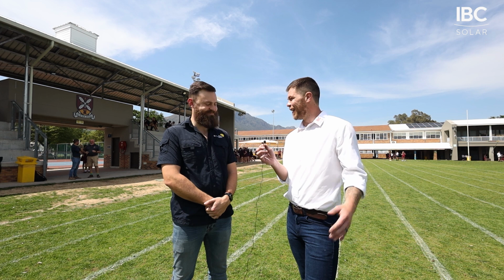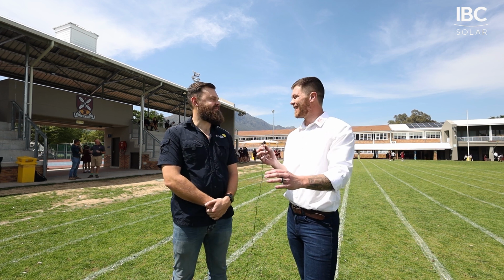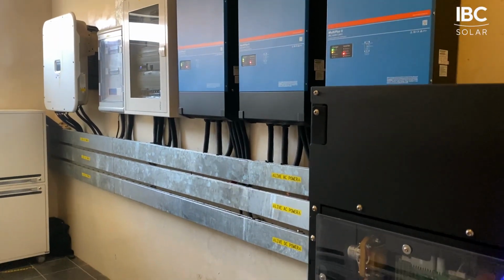We got to site this morning at Eikestad Primary School, and as we walked into the inverter room, the first thing we saw was 3 red lights. When we got here and started taking photos for the promo shoot, we saw that all 3 of the inverters had gone into an error state, and the error was a low battery alarm, which immediately points to the batteries.